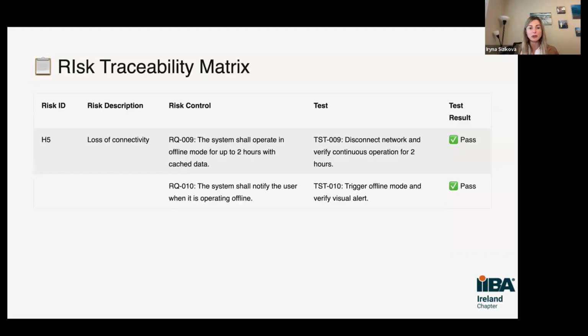Last one, loss of connectivity. For example, the system shall operate in offline mode for up to 2 hours with cached data. How do we test it? We disconnect the network and verify continuous operation for 2 hours. If we get normal work with some output, we say the test is successful. If not, the test fails and we decide about further mitigations. Then the last one: the system shall notify the user when it is in offline mode. So we trigger offline mode and verify this alert. As soon as we get the alert, and the user understands that they are in offline mode, it means we helped the user with the information.